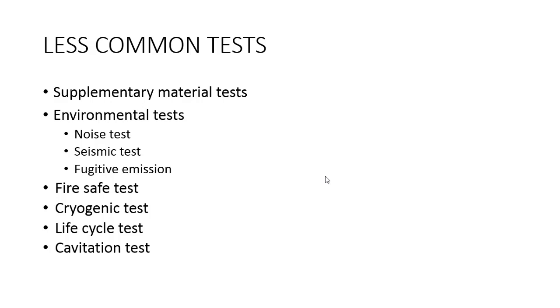Next is a cavitation test. Guidelines for testing is as per ISA S75.23. Important parameters are calculated and used for the same trim design in different size and ratings. So all the sigma values are calculated from the cavitation test, and it can be extrapolated to other sizes and ratings, but with the same trim design.